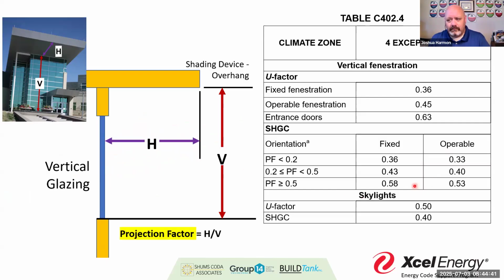Because if you chose to go minimum and you're expecting these windows to be covered, and again, I've told you I've done this before, where I had an all glass building, and they put the windows on the wrong side, right? Each side of that building had its own specific type of window that was going to be installed, with its own U factor and solar heat gain coefficients.